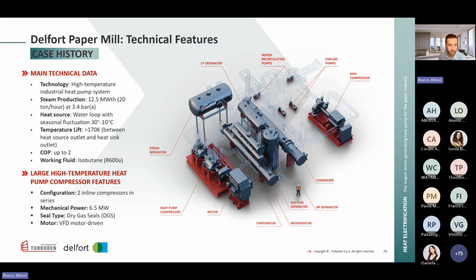The working fluid, as said, is isobutane. In this case, we are using an inline compressor with 2 cases in series with a mechanical power of 6.5 megawatt electric. As you can see on the right, you see quite well the layout of the system. On the bottom left, there is the compressor skid with an electric motor. In the center part, there are all the heat exchangers, both the evaporator, the condenser, and the separators internal to the heat pump circuit.